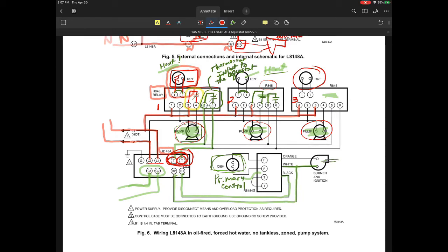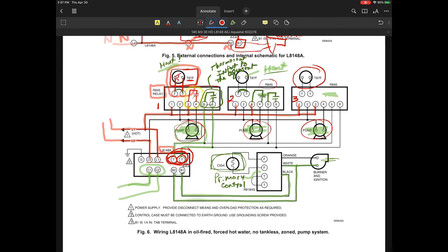So if I walk up to a boiler in the field and I take my meter out and check between the T and T terminals, if there is a demand, I am fully expecting to see 0 volts on those T and T terminals. It would be no different than if I took a jumper wire and jumped it from T to T. Your meter would be measuring a potential difference, and of course if there's a jumper on there, there is no potential difference.